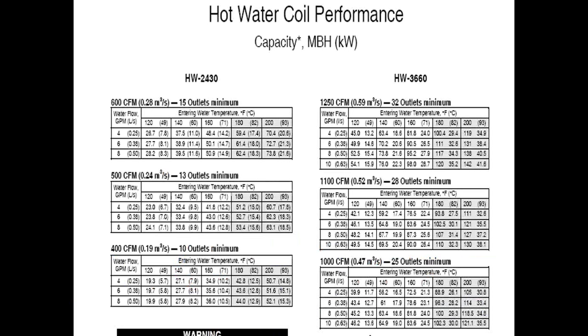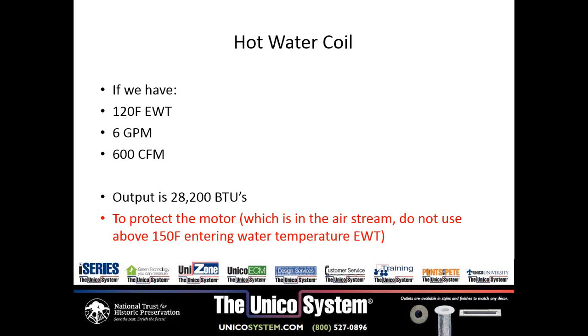Again, our hot water coils, we had mentioned this before with the geothermal. We make these to work with the entering water temperature, the CFM, and the gallons per minute. So if you take a look here, 120 degree water with our 3-ton system at 6 gallons per minute puts out 27,000 BTUs. If we can crank that up to 160, we almost double. We get to 50,000 BTUs output. Now again, that's output, not as we typically rate furnaces at 70% efficiency. Again, in that example, 120 degree water, we get 28,000 BTUs. Remember, to protect the motor, which is in the airstream, we don't recommend above 150-degree entering water temperature.